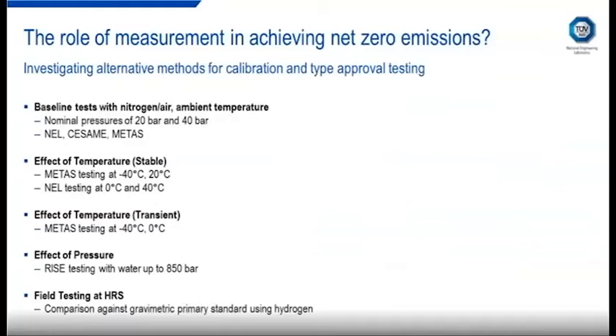We also did tests where the effect of temperature was isolated. So we studied the effect of temperature under stable conditions from temperatures of minus 40 up to 40 degrees C. So an overall range of 100 degrees. Next, we also investigated the effect of temperature under transient conditions. So this was done by introducing gas to the flow meter at very low temperature. So the meter was initially at ambient temperature, and there was no time allowed for the flow meter temperature to stabilize. So measurements were taken as the temperature was adjusting to the incoming gas.